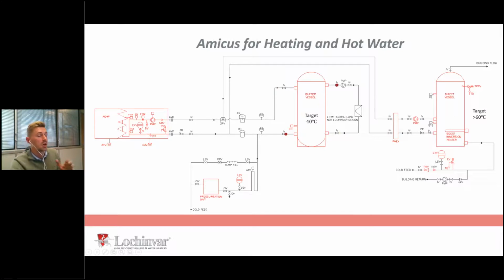So a lot of people will look at that and think it looks very familiar. System boiler in a house, right? You've got your heating zone, you've got your hot water zone, and you've got a hot water priority format. And that's the kind of application, through the flexibility of this style of unit, that air source heat pumps are now capable of. So we've got a 400% efficient heating system. We've got a 320% efficient hot water system. The carbon credentials of a building using technology like this, unless you've got outrageously bad insulation on it, are going to be fantastic. So that is heating and hot water from an electric air source heat pump.